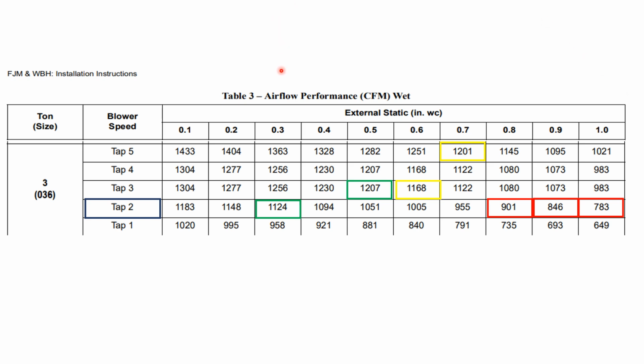Now, what I want to point out real quick is when you do that, anything over 0.3, keep in mind, ICP does not want any of your equipment higher than 0.5, period. If you're in cooling mode, the most you can go is 0.5. Keep in mind, this unit will operate into the 1.0. But if I look at 0.5, which is where they want it, and I'm at speed tap 2, then that means, let's say my static pressure was around 0.52 or 0.53, and let's say I'm at speed tap 2, I'm putting out 1,051 CFMs, not the 1,200 I think I'm doing. But let's say I'm in a high static of this 1.0, that unit's only putting out 783 CFMs.